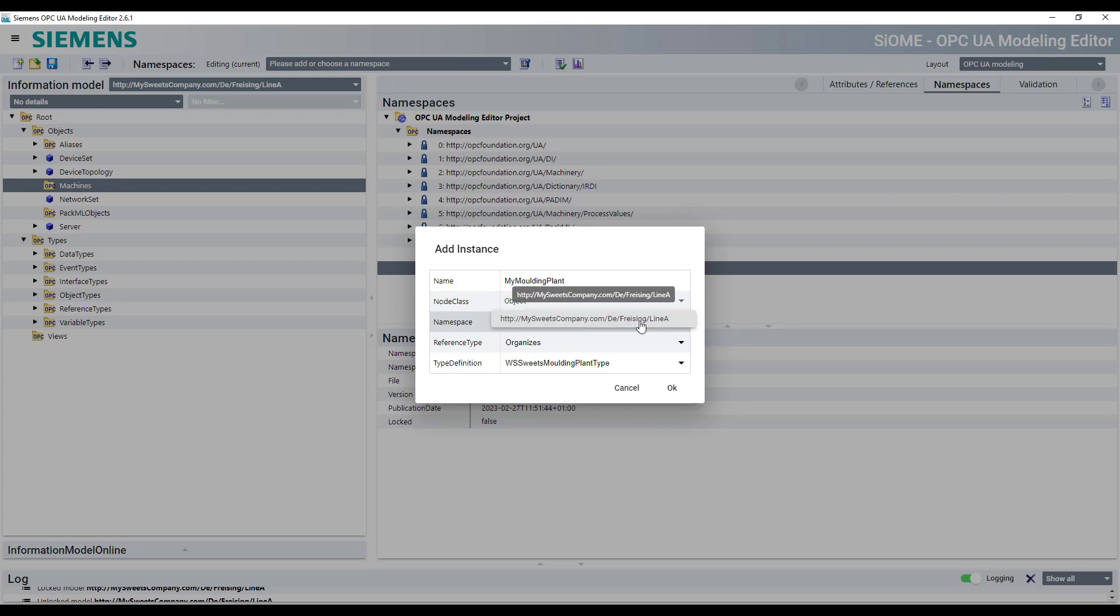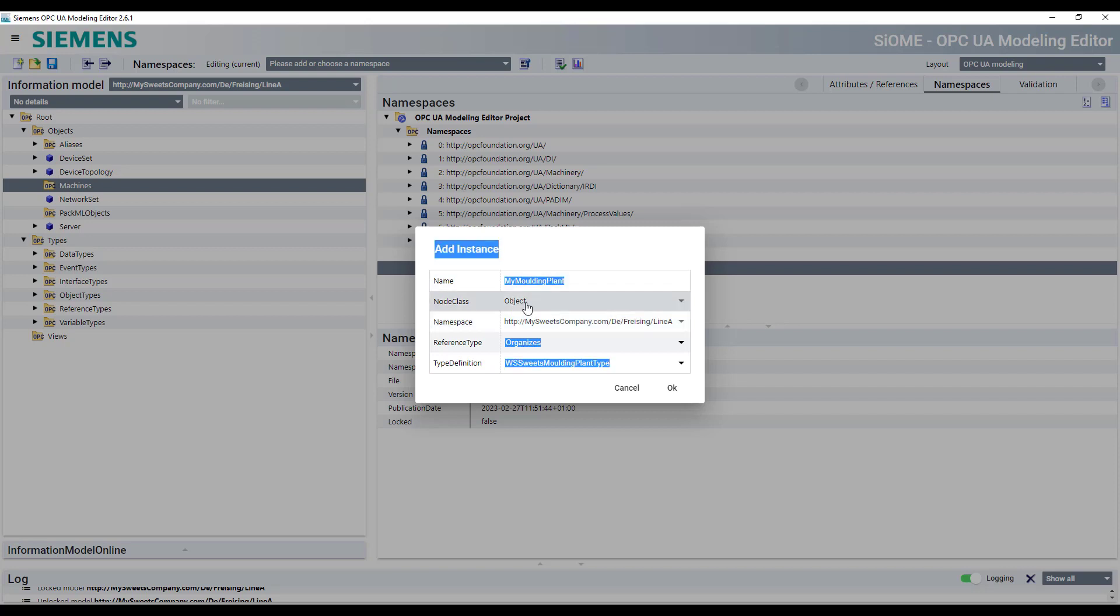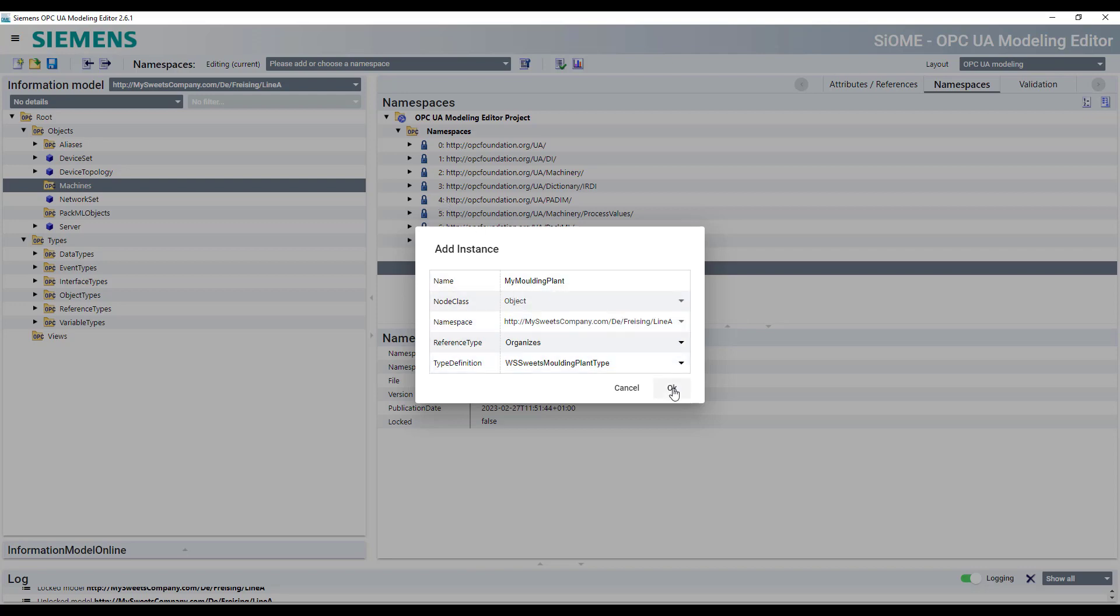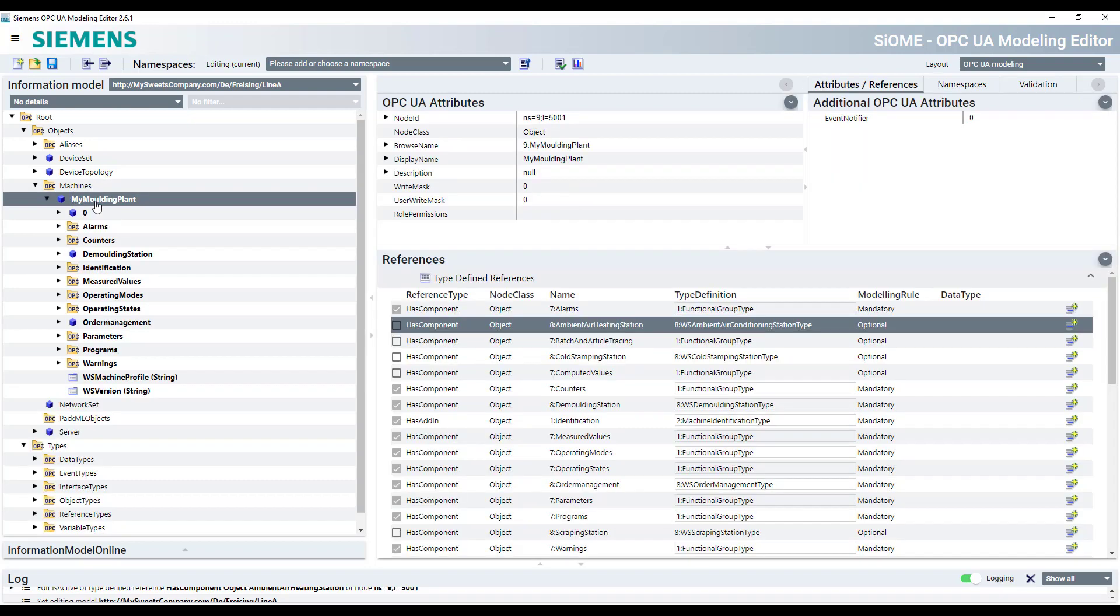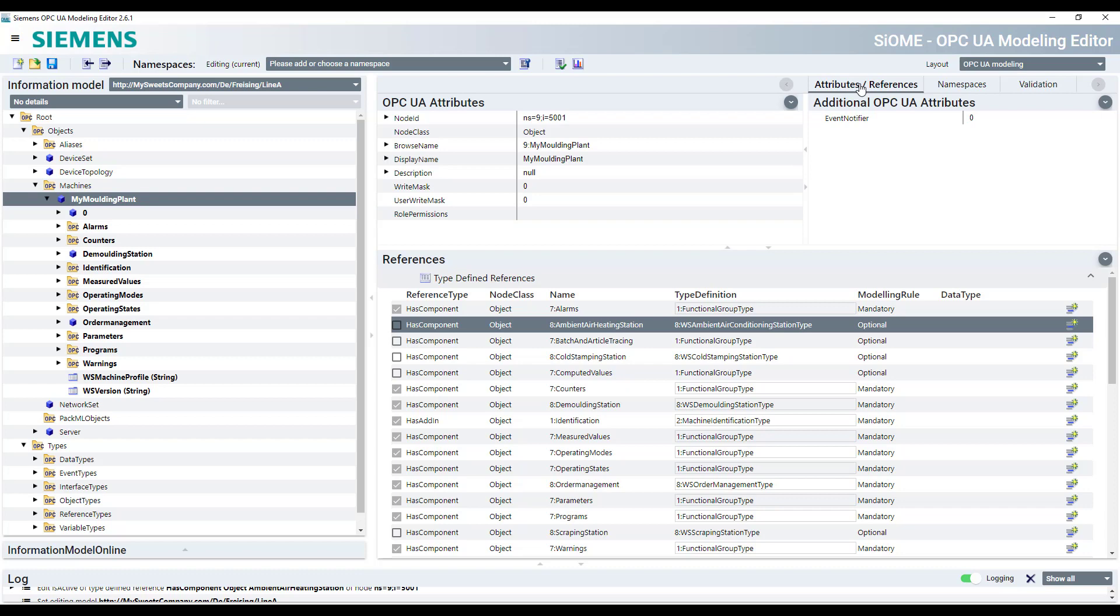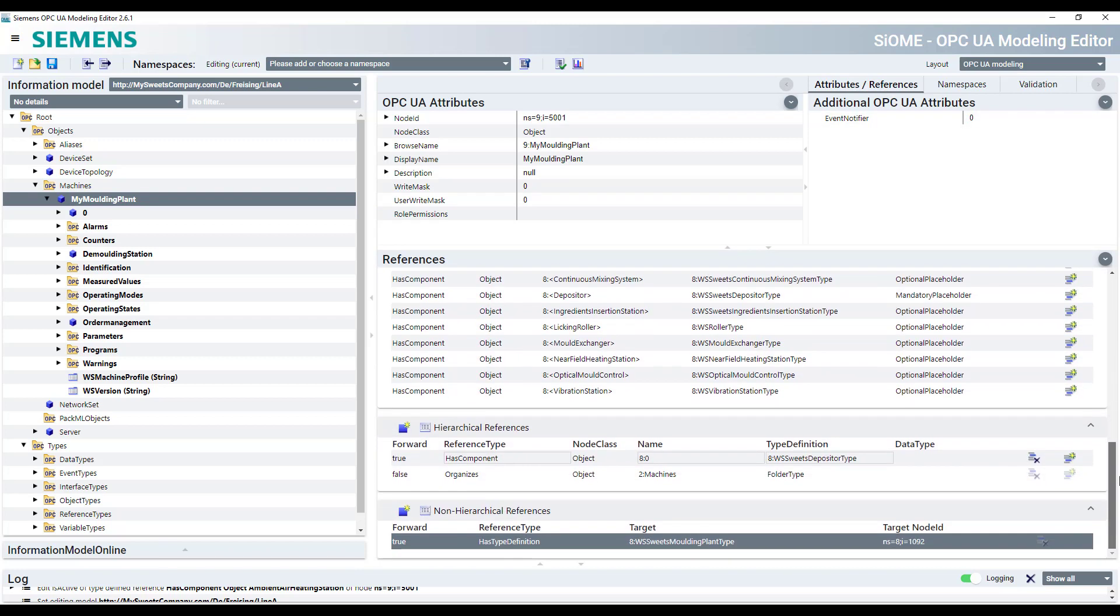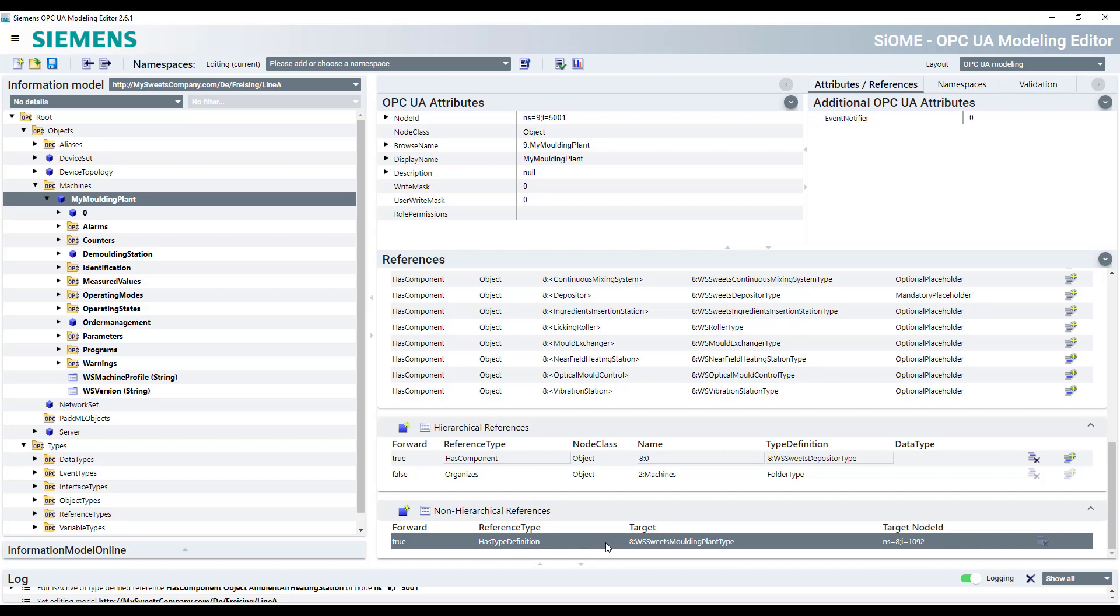So make sure you really select the right namespace. In this case, that's the only one which is available because this is the only unlocked namespace, but sometimes you have other namespaces here unlocked accidentally. So make sure you select the right one. Now immediately you get a new machine underneath the machine folder. You can always check what's the type of certain objects. If you go to the attributes and references tab and then scroll down to the non-hierarchical references and there you find the type definition of a certain object.